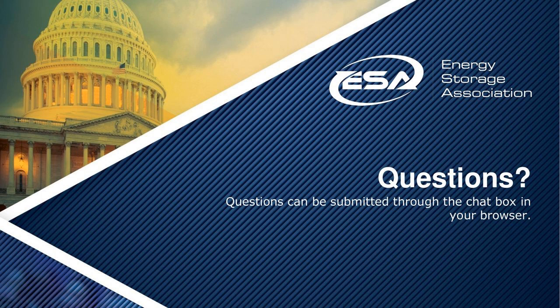That is the one referenced in the code, but if you had done some other version of large-scale fire testing, I suppose you could go to the AHJ and ask if they will accept it. It's maybe a little easier to go with one identified in the code as an acceptable method, but it's probably not the only one. Either way, you'd have to seek approval from the AHJ—they have the final say. Even with 9540A, the AHJ still has to approve it. When we do a 9540A, there's a report we provide, and the client has to present that to the AHJ, who still has to review and approve it. So that's always an option, though it tends to be more difficult, but not impossible.